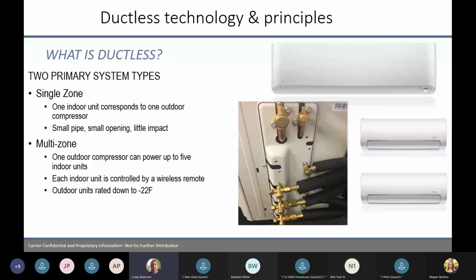So you'll notice in this picture on our multi-zone, which is nice about our units, we have master valves on the top, and then each unit has its own separate valves as well. So if you put a multi-zone unit in and you have an extra port for future, you can go back and add an extra head without pumping that unit down and doing all that stuff. You can add it on, do your vacuum, away you go, open your valves and get that other unit started. If you're having a problem with one of the indoor heads, you can isolate that valve and just take that head out of the equation. So nice little feature on our multi-zone.